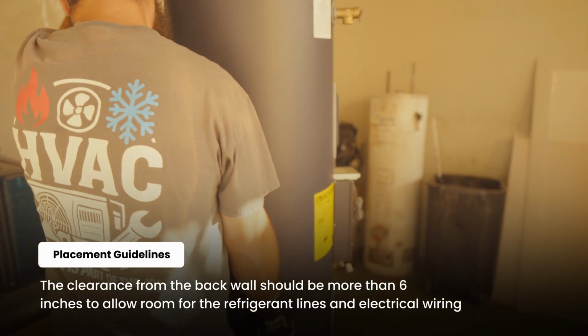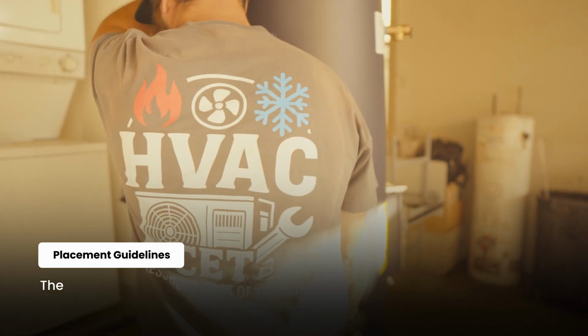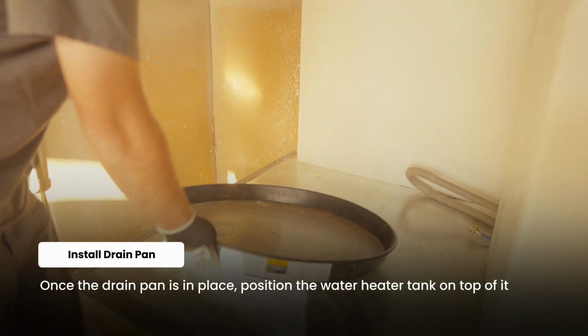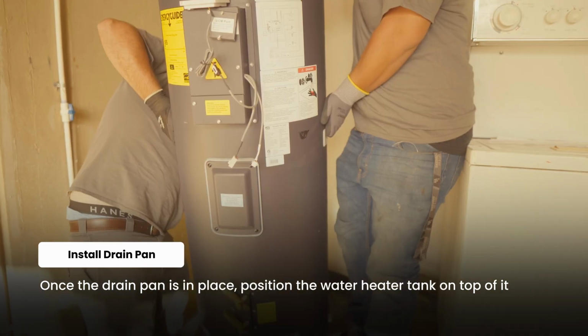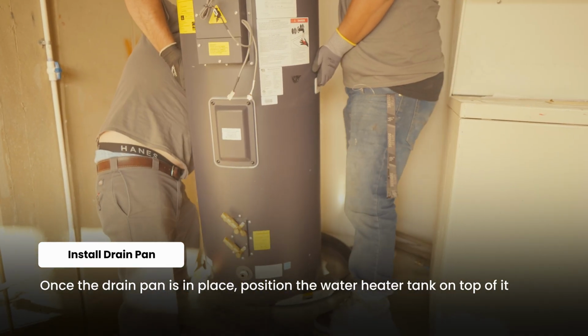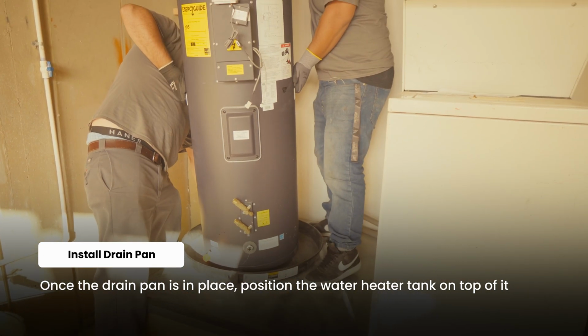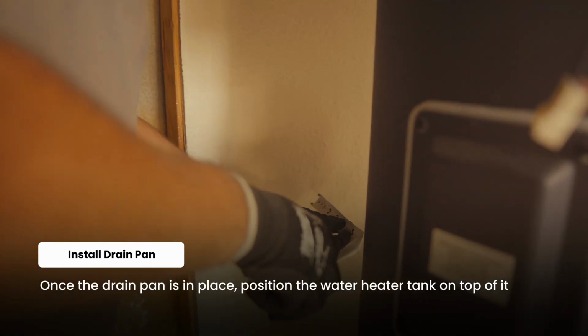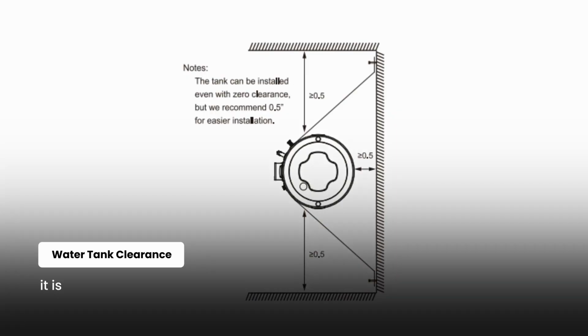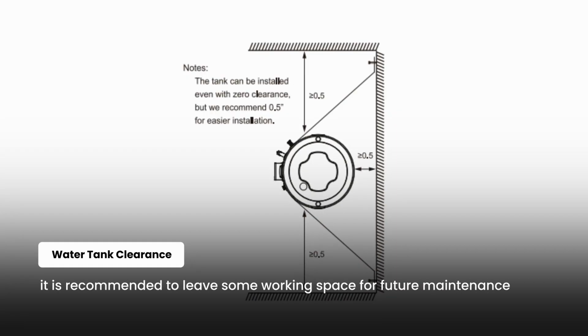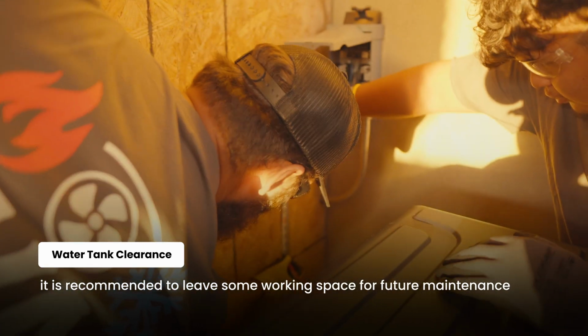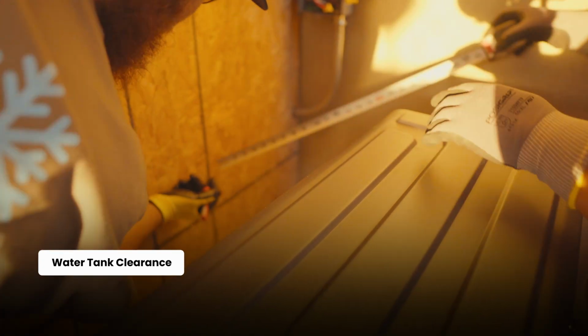Next, we will set the water heater tank. Before placing the tank, install the drain pan in the desired location. Once the drain pan is in place, position the water heater tank on top of it. Although this water heater can be installed with zero clearance, it is recommended to leave some working space for future maintenance. After that, identify the best location to route the wiring and, if needed, drill the appropriate hole.